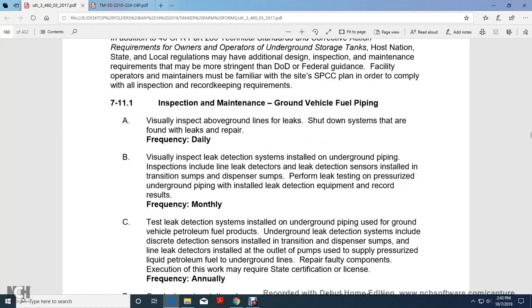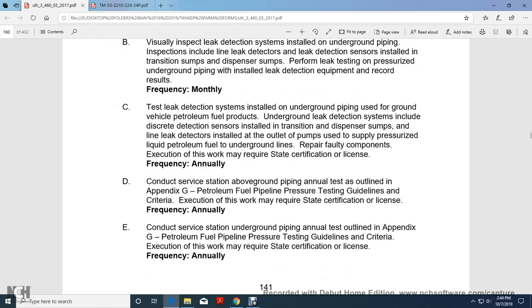Inspection and maintenance of the ground vehicle fuel piping. Visually inspect the aboveground lines for leaks, shutdown systems, and repairs daily. Visually inspect the detection system installed in the underground piping. The inspection includes the line leak detectors and leak detection sensors installed in the transition pump sumps and dispenser sumps. Perform leak tests on pressurized underground piping when installed with leak detection equipment, and record results monthly.